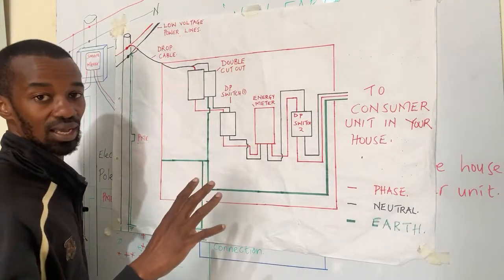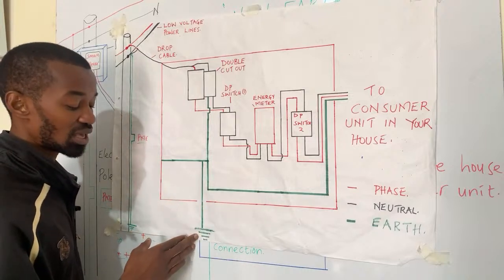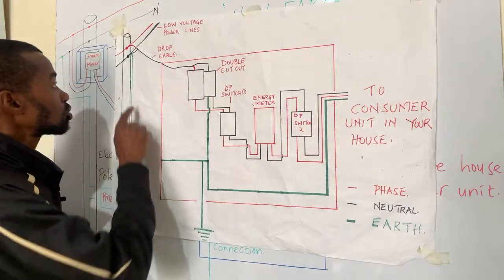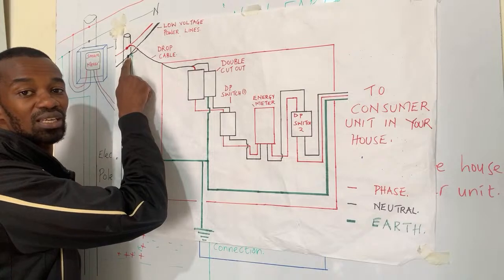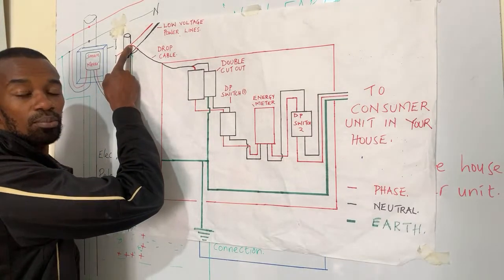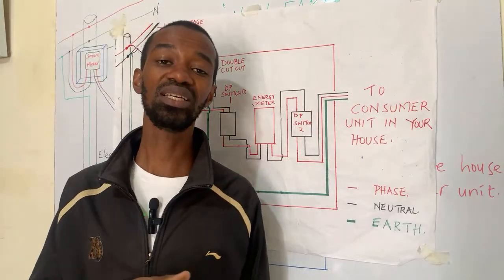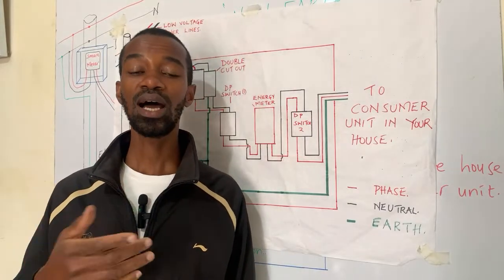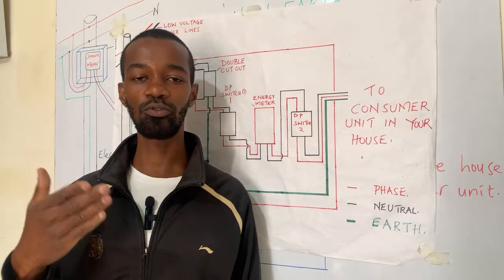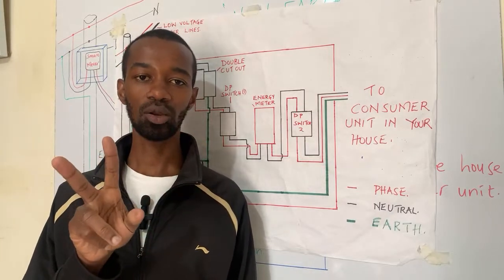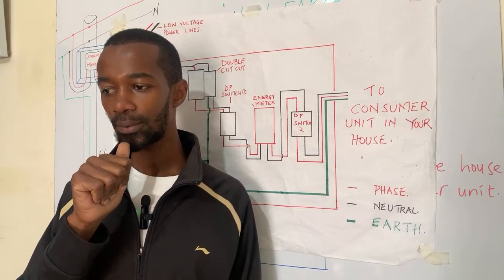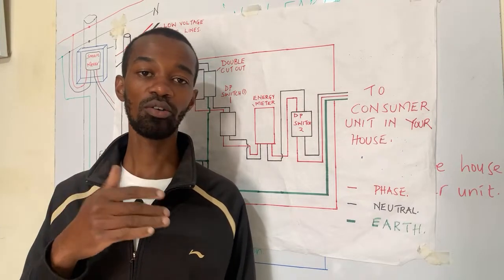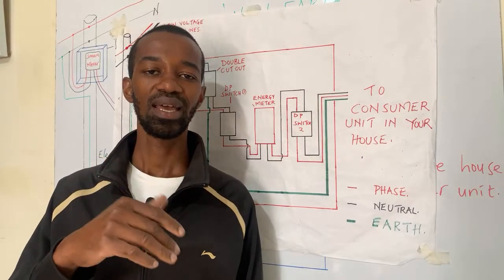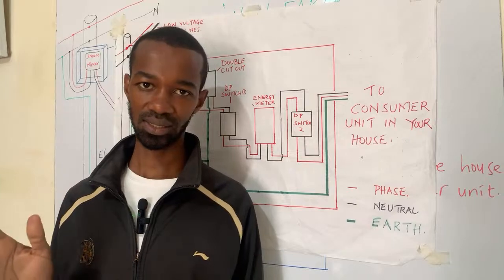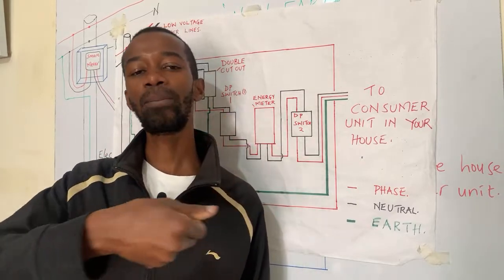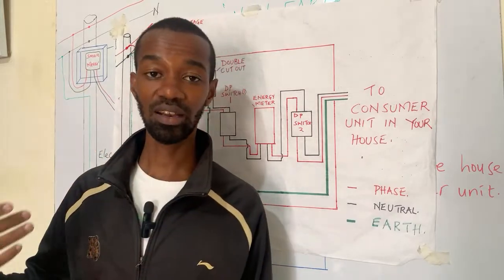Because an earth error is whereby excessive charges will not find their way to the ground and back to the transformer. So if there's a loose connection on the neutral, it is very, very dangerous as compared to a loose connection on the phase, because a loose connection on the phase simply translates to no electricity. So if a fuse at the transformer, this is an LV fuse or low voltage fuse, is burnt or open, or as we normally say, it has blown because of an overload or a short circuit, that in general means there's no electricity, all right? Because there will be no return path to the electricity if the electricity itself is not present, all right.